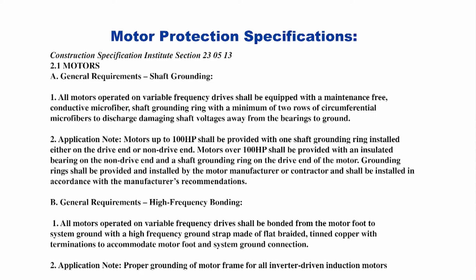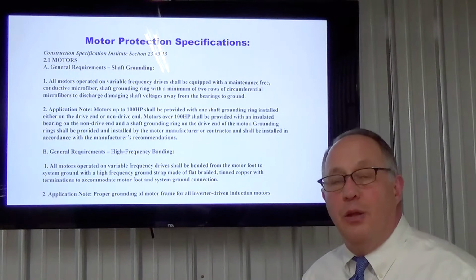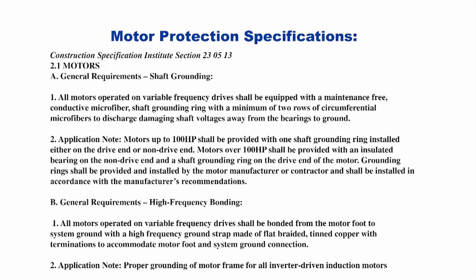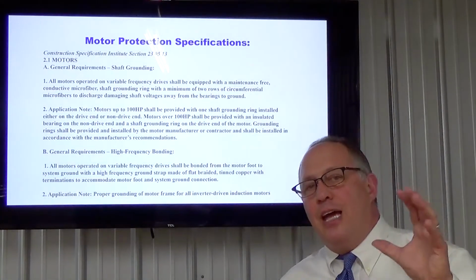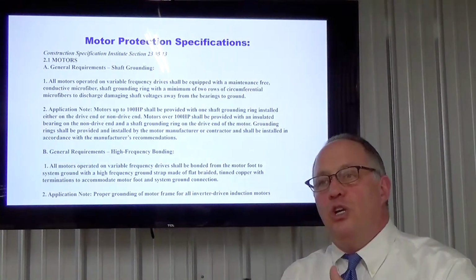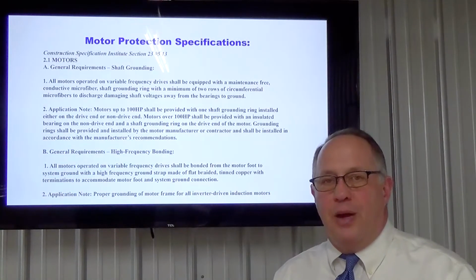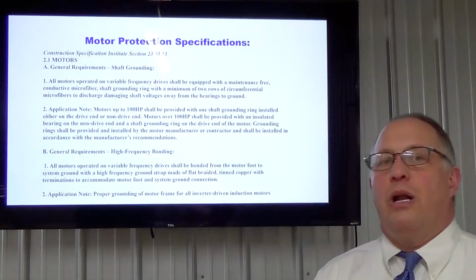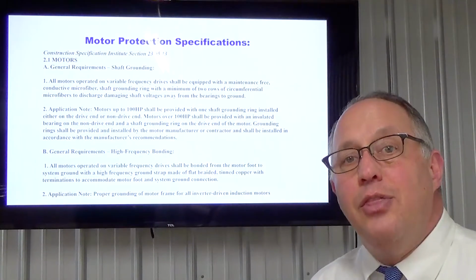As we had said earlier, one of the things you want to walk away with is the specifications. This has to be included with the motor itself in the motor specs. Typically, section 2305.13, motors, general requirements, shaft grounding. All motors operated on variable frequency drives need to be equipped with a maintenance-free conductive microfiber shaft ring with a minimum of 2 rows of circumference microfibers to discharge any voltages. Now that's using what we call the best practices. If you want to use something other than that, there are plenty of manufacturers and equipment that can provide you with the language. What I wanted to point out here is that it needs to be included in the motor specifications.